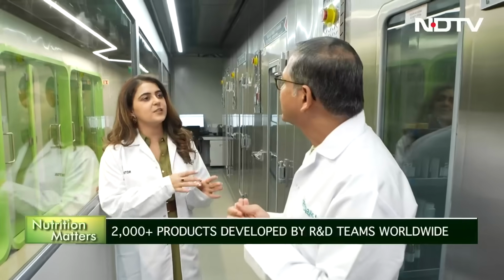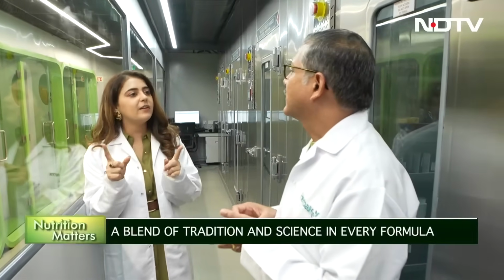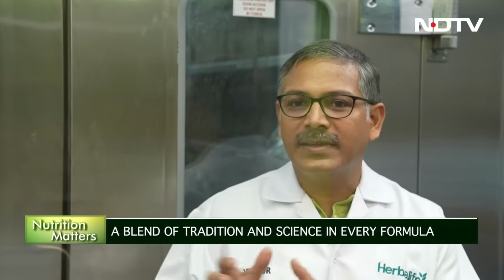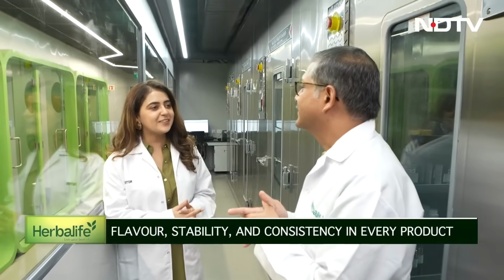So that means that every chamber has its story of how many months you will put in to see and test that shelf life that exists in the market. Yeah, so based on the stability condition, the respective batch passes, and based on that the shelf life of the product will be decided. That's wonderful. That's very rigorous standards that you are maintaining here.